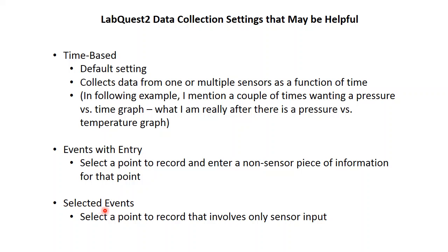The last mode we'll look at briefly is selected events. In selected events, it takes all the data from the sensors — you don't have to enter anything. It just takes the ones you want. This is useful if you don't want to collect data forever and have huge files. So if I'm heating something up and watching the pressure and temperature, I just go over every few minutes and click a selected event to take a pair of data points.